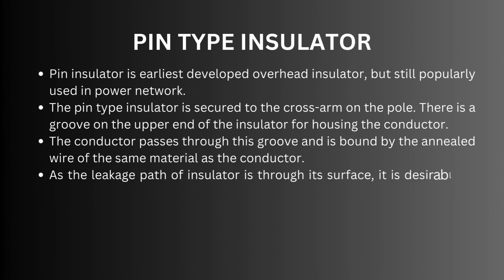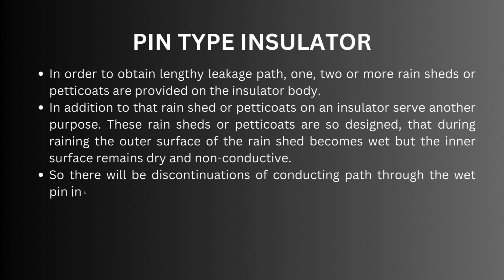As the leakage path of the insulator is through its surface, it is desirable to increase the vertical length of the insulator surface area for lengthening the leakage path. In order to obtain a lengthy leakage path, two or more rain sheds or petticoats are provided on the insulator body. These rain sheds or petticoats are so designed that during rain the outer surface becomes wet but the inner surface remains dry and non-conductive, creating discontinuations of the conducting path through the wet pin insulator surface.